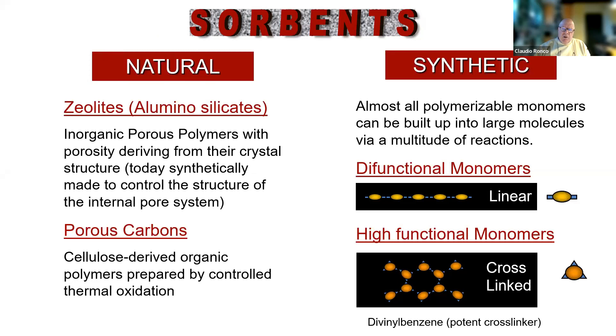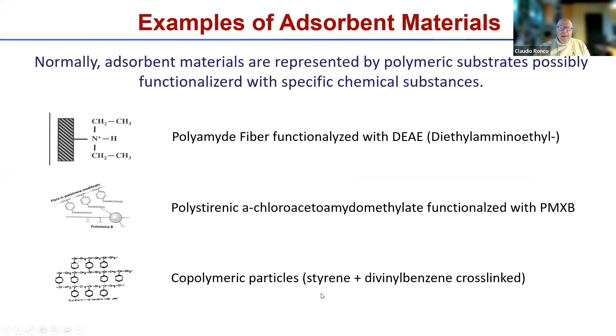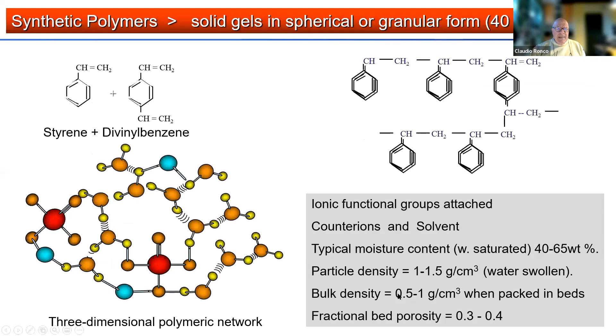Sorbents can be natural or synthetic. Most of the sorbents we use today are synthetic with difunctional monomers that are linked, or highly functional monomers that are cross-linked by divinyl benzene. Examples of absorbent materials include polyamide fibers functionalized by DEAE, polystyrenic fibers functionalized with polymixin B, or copolymeric particles like styrene and divinyl benzene cross-linked. The monomers can create a three-dimensional polymeric network, and normally the fractional porosity of the bed is 30 to 40 percent.